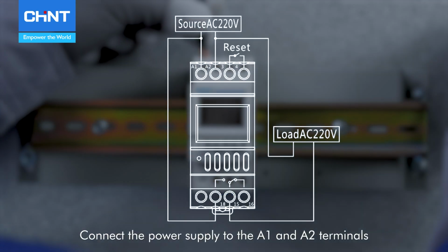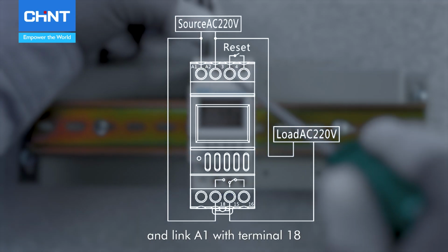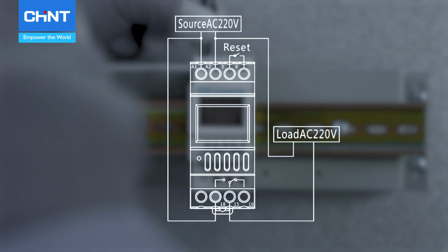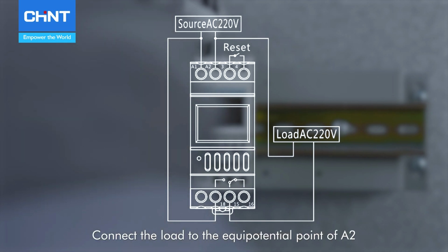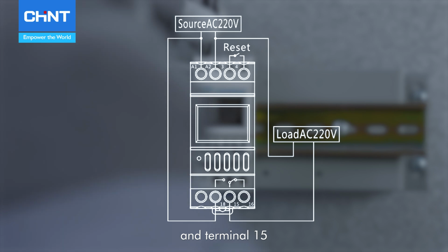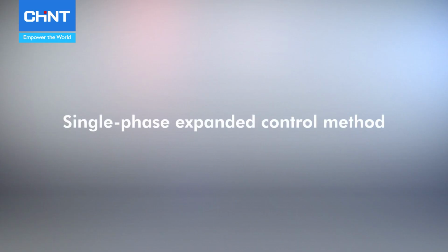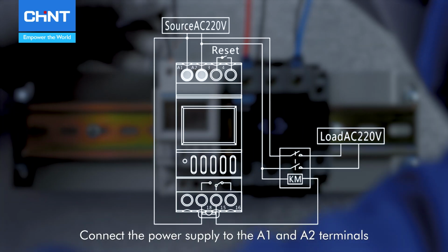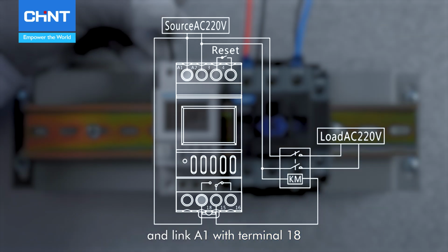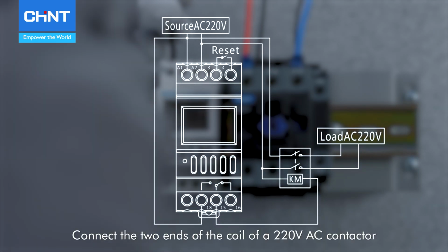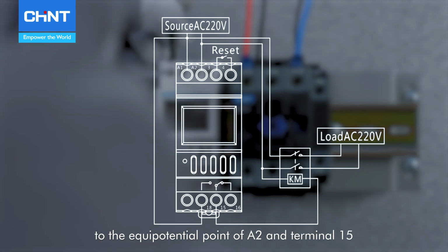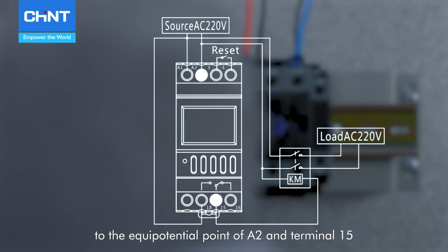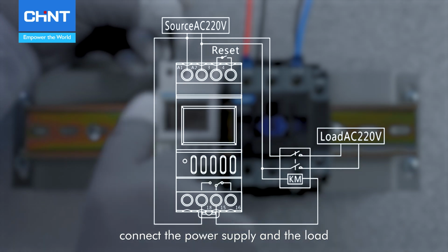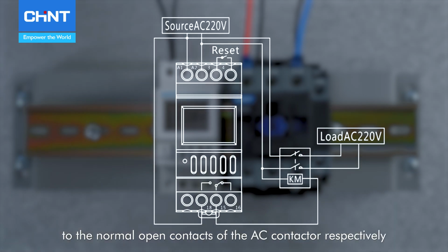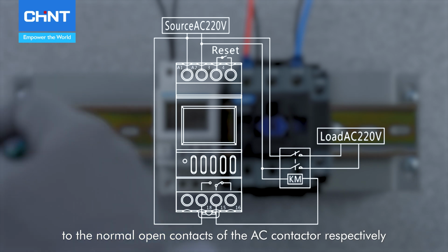Connect the power supply to the A1 and A2 terminals and link A1 with terminal 18. Connect the load to the equipotential point of A2 and terminal 15. Connect the power supply to the A1 and A2 terminals and link A1 with terminal 18. Connect the two ends of the coil of a 220 volts AC contactor to the equipotential point of A2 and terminal 15. Connect the power supply and the load to the normal open contacts of the AC contactor respectively.